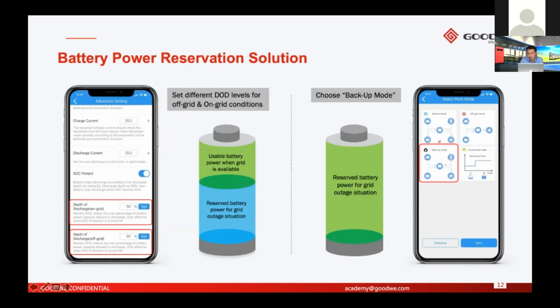Another solution is backup mode. For hybrid or AC coupled systems, in the application you have basic settings with four basic operation modes. The first is general mode, then off-grid mode, and also economic mode. Here we don't talk about the details, we only focus on backup mode. Backup mode means you reserve all the battery power to be used when the grid is off. So if the grid is normal, the battery will not discharge. It will only charge, to make sure the battery has enough power when the grid fails.